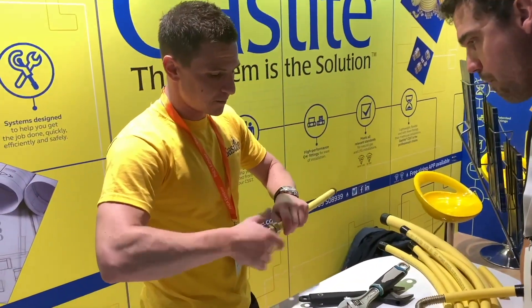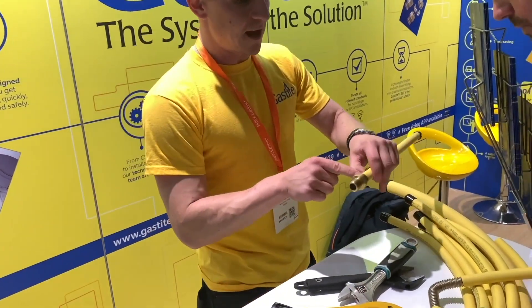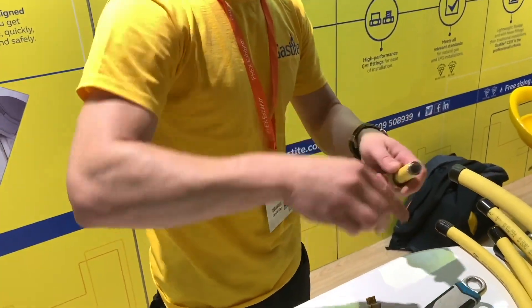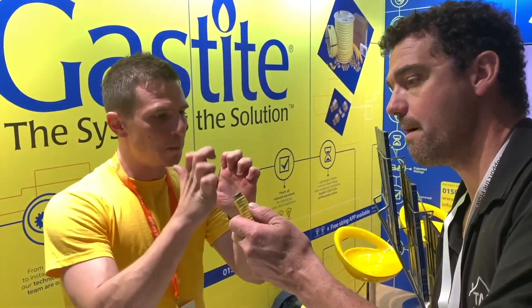These Gastite fittings are completely reusable. If you've made a bad cut, you can redo it. Once the fitting is tightened, that gap disappears, and you have a seal on both the lower and upper part of the corrugation - you haven't just got one seal, you have a double seal.